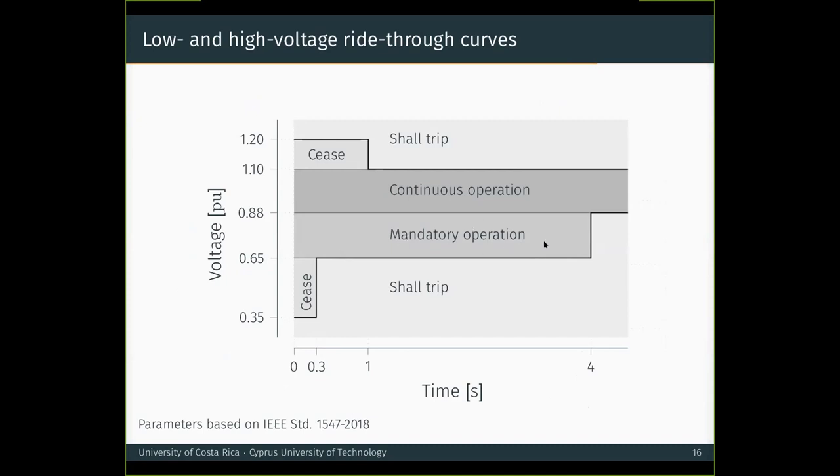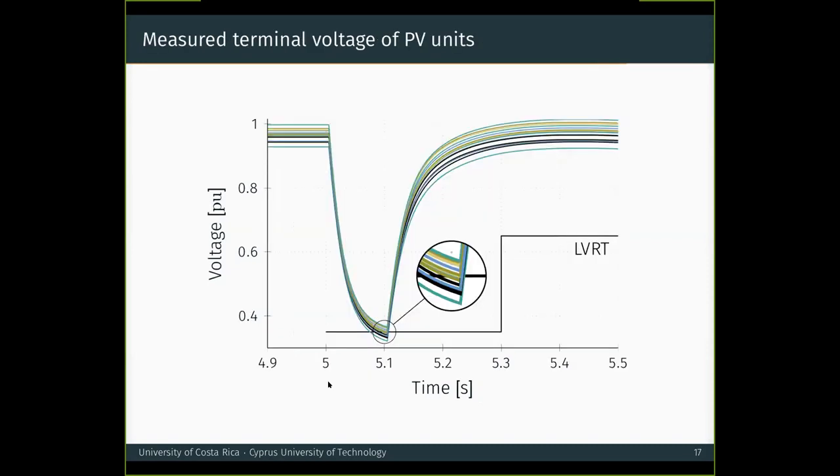However, if the voltage drops below this lower line, which is a low voltage ride-through curve, then the units should trip. With the exception of this limit, which was raised from 0.3 to 0.35, just to obtain more diverse responses, all parameters are based on the IEEE 1547 standard. So knowing this, let us return to the terminal voltages. When we zoom in and superimpose the low voltage ride-through curve, we can see that some units stay above it, but others go below and therefore should trip. And how can we determine what fraction will do that? Again, we need to model all voltage levels. So from this picture, it is to be expected that some units trip while others do not.